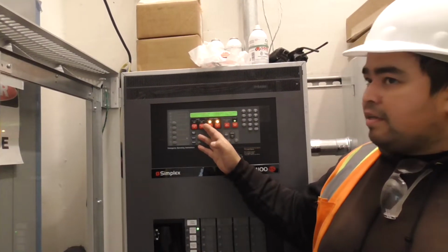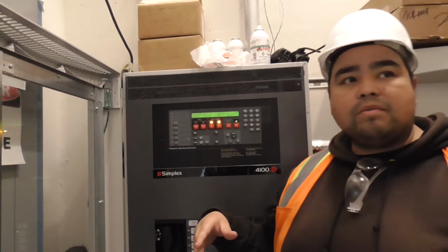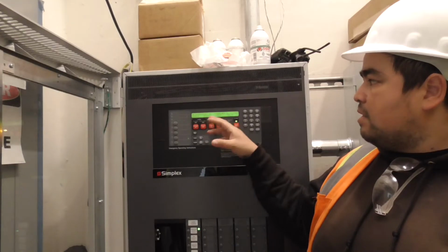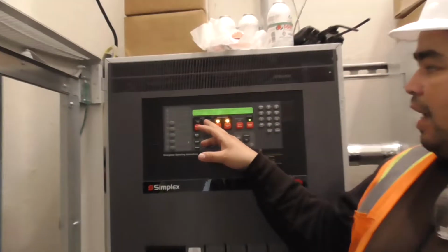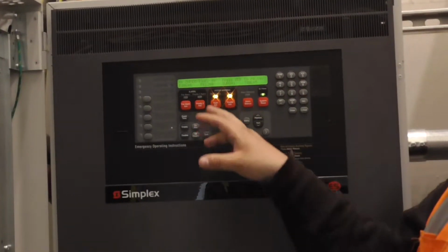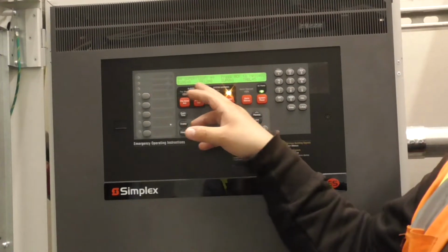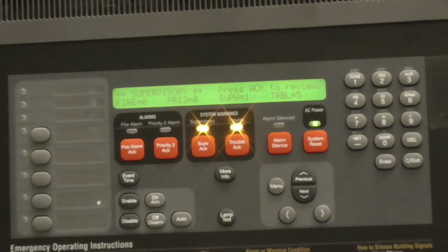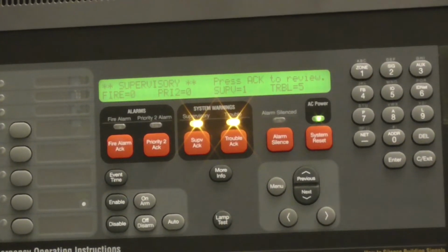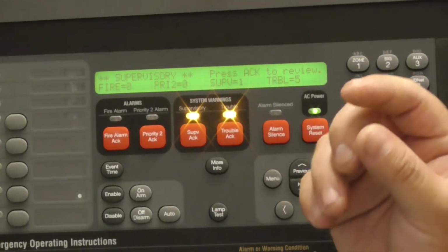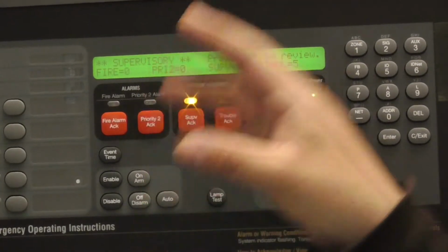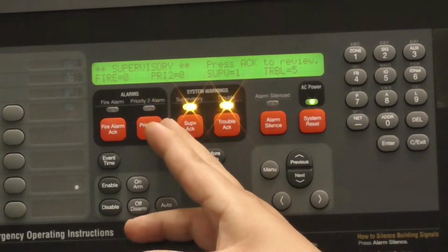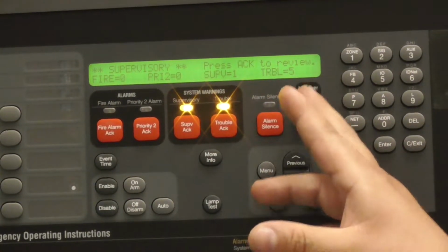Priority 2 event. In this building they have COs, so carbon monoxide detectors. Right? So if they get a CO event, it's going to light red here, it's going to flash, it's going to say priority 2, and it's going to say gas detection. And what's going to happen in the room, rather than getting a code 3, you're going to get a code 4 in the room. And it's going to come in red just like here, it's going to report to the PD, and then someone's going to need to come and acknowledge it the same way. Alarm silence, system reset.